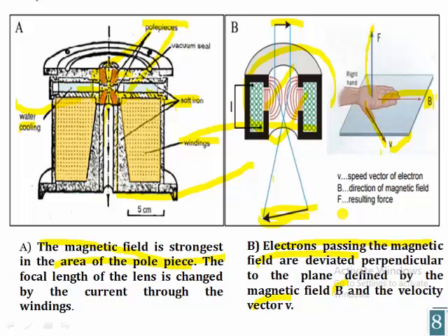acts as a condenser lens, as we have seen, and which will determine the overall brightness. The first lens will determine the overall brightness of the specimen. After that, electrons transmit through the specimen and the objective lens, which will produce a primary image. Then we will get a final magnification, and it is determined by the projective lens. And we will capture that image on a CCD camera, right?